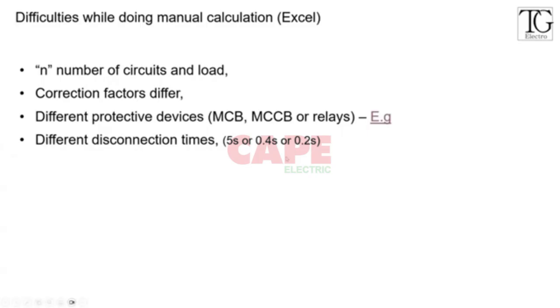Now, there is another problem where you have different disconnection times. Suppose you have to get it for 5 seconds or 0.4 seconds or 0.2 seconds, it is going to differ. For hospitals, if you don't care about the disconnection time and you keep everything at the minimum 0.1 seconds, that is fine. But do remember that if there is a fault at some X circuit, it is going to affect even your main panel. So that selectivity, or I would say discrimination, will not be there if you keep everything at the same disconnection times.